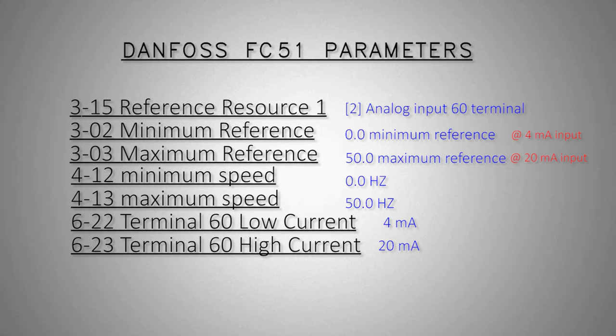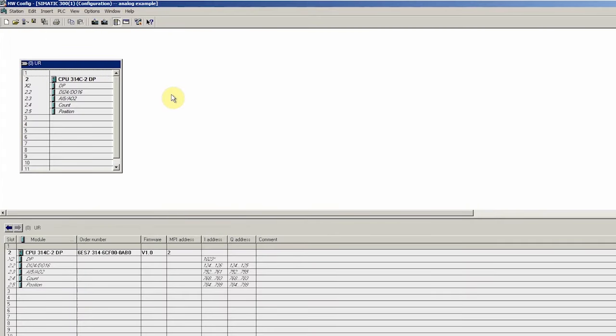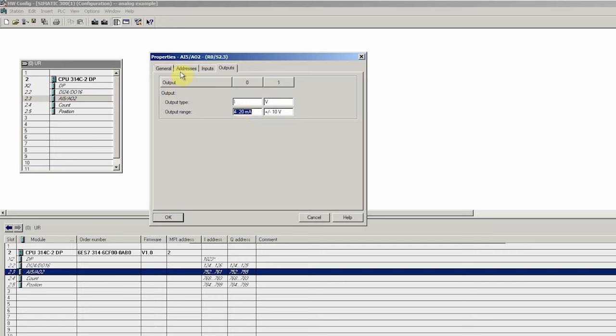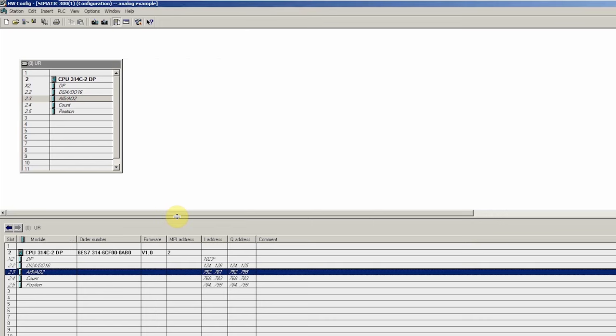Now let's see the programming for the PLC. First we will create a new project in the Simatic Manager and open the hardware configuration. If you are new or want to learn how to create a new project in Simatic Manager, you can click the card in the upper right corner. Moving on, if we open the properties of the analog channels, we can see that by default the analog output channels are set to 0 to 10 volts. We will change channel 0 to a current output with a 4 to 20 mA range.